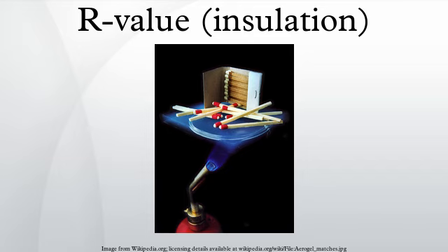Loose cellulose, fiberglass, and rock wool all possess a value of roughly R-2.5 to R-4 per inch. Straw bales perform at about R-1.5. However, typical straw bale houses have very thick walls and thus are well insulated. Snow is roughly R-1. Brick has a very poor insulative ability at a mere R-0.2, however it does have a relatively good thermal mass. Typical values per unit thickness are given for materials.